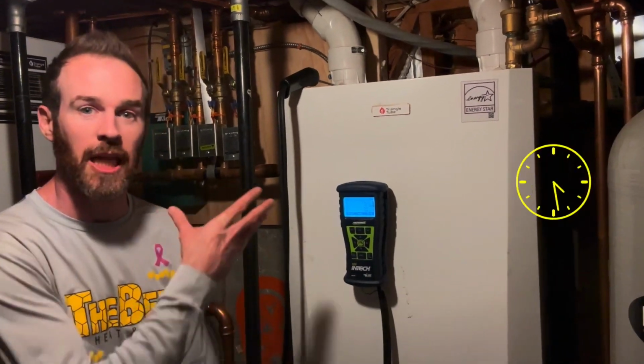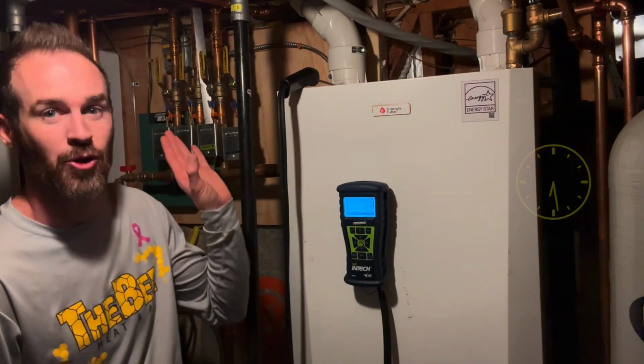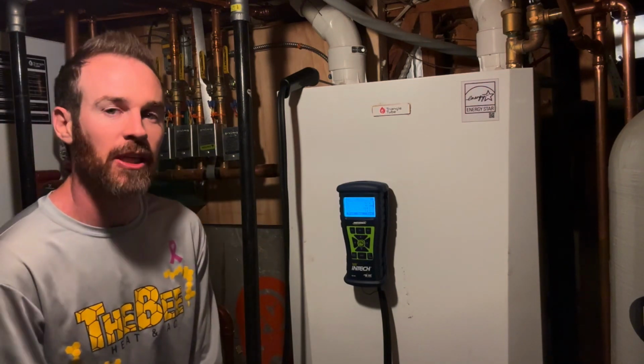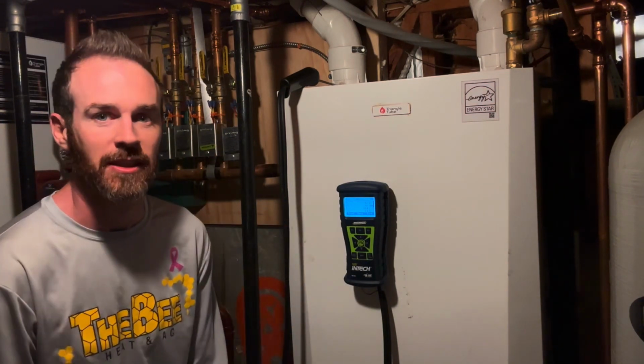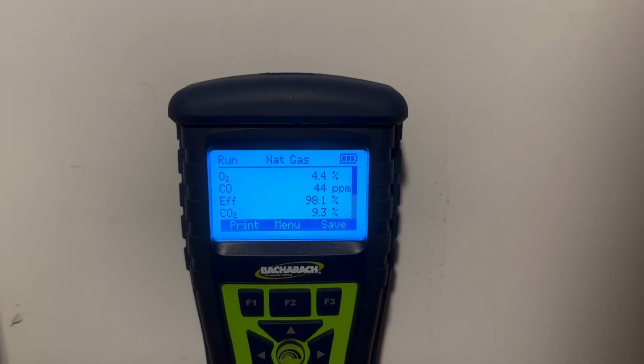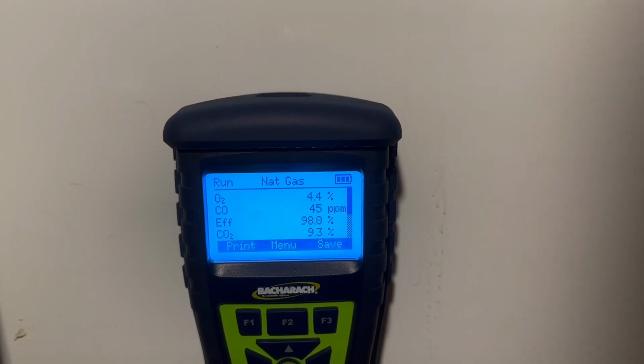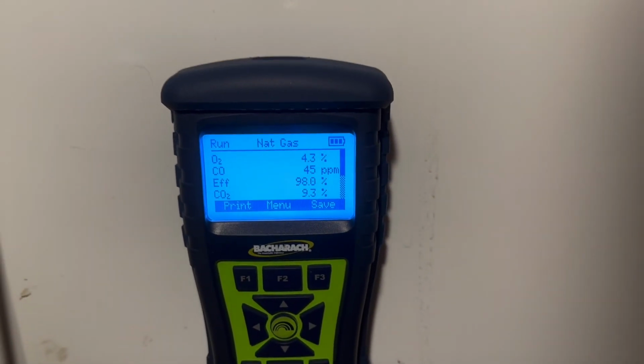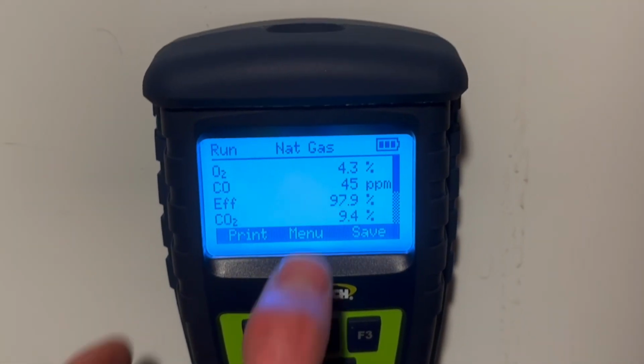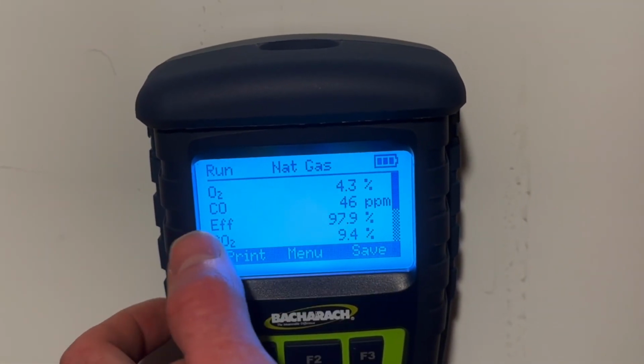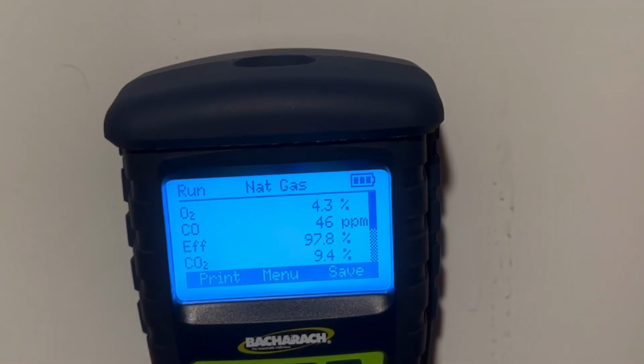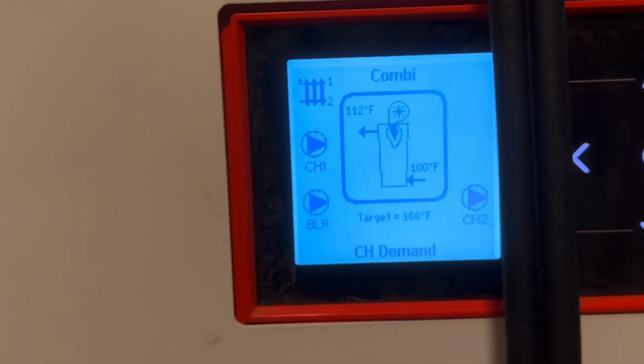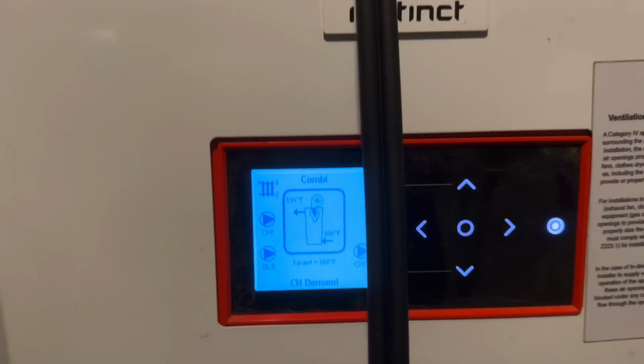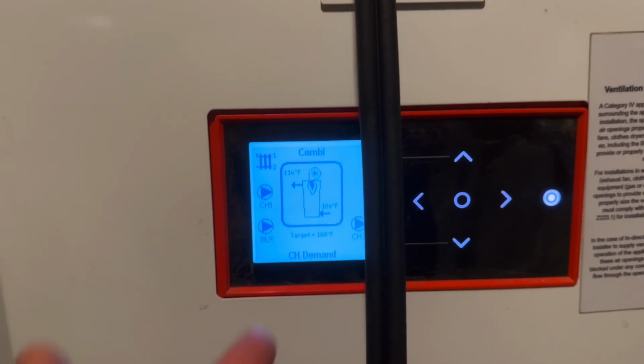than normal. So we're gonna let this run for a few minutes, and then I'm gonna show you what the actual numbers are of this so you can see what the efficiency is. So the system just started running, literally just fired up, and these are the combustion analysis numbers we're looking at. As you can see, the ppm is actually a little bit high, but that's gonna take a while to adjust until it's actually running more efficiently. And part of that is because of the temperature of the heat exchanger itself. So you're actually getting more condensation because the boiler hasn't technically warmed up yet.